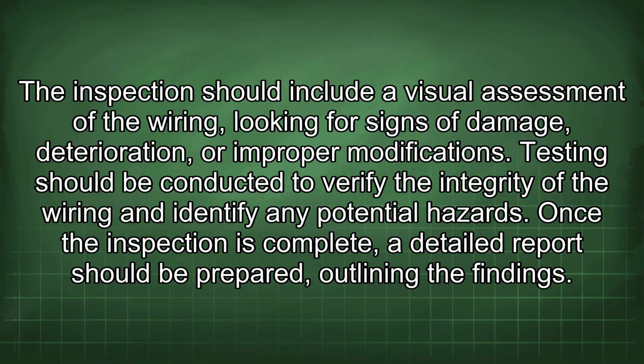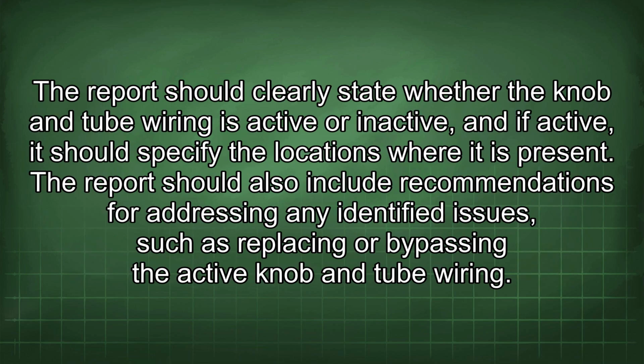Once the inspection is complete, a detailed report should be prepared, outlining the findings. The report should clearly state whether the knob and tube wiring is active or inactive, and if active, it should specify the locations where it is present. The report should also include recommendations for addressing any identified issues, such as replacing or bypassing the active knob and tube wiring.